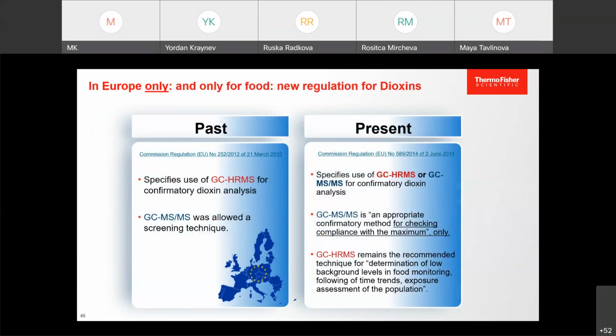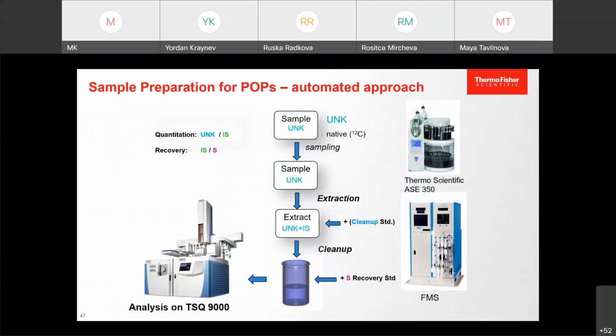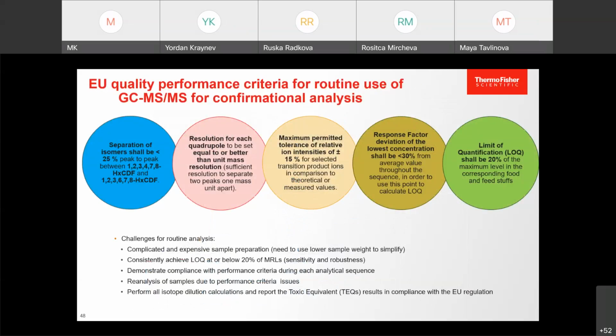That's why we are using our TSQ 9000 with advanced ion source. You can see here our POPs, persistent compounds, how we are cleaning them up, extracting, sampling, and then analyzing by TSQ 9000. Here you can see factors which should be met. This is the EU quality performance criteria, which your instrument should pass when you would like to analyze dioxins, but only in food, not environment, because for environment it is not allowed to use it. You should use a dual focus instrument.